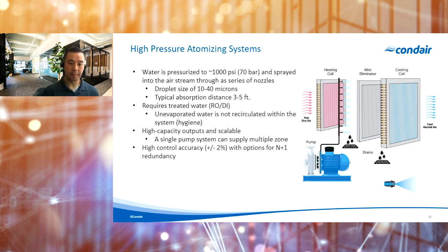Now, because this system is actively atomizing the water, the evaporation efficiency here will depend on the contact time between the air and the water. So we typically see a minimum of about 3 to 5 feet of unobstructed airway length in order to achieve a decent evaporation efficiency. So with this system, again, any unevaporated water, primarily for hygiene reasons, is not recirculated within the system. Any water that's not evaporated will typically get caught by what we would have downstream as a mist eliminator or potentially the cooling coil to prevent any water droplets from carrying past that section, potentially wetting components downstream.